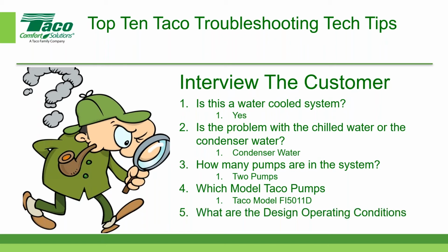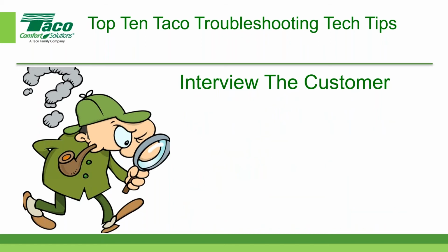I have a few more questions for this person. What are the design operating conditions? And in this particular example that we're talking about today, let's assume the customer comes back and says, well, it's 1,000 gallons per minute at 80 feet for each pump. So you've got 2 pumps in the system. It's condenser water. Look, we're getting all kinds of information by just going through this interview process. And the pumps are connected in parallel. I don't know that yet, by the way. He just says he's got 2 pumps. And they're 1,000 gallons per minute each. That's how each pump is rated.